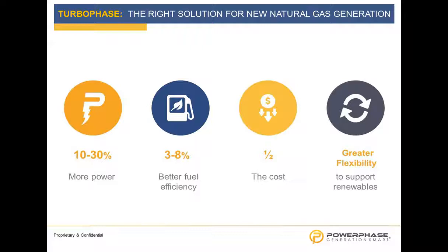Our desire here is to burn gas for more gas-fired generation, right? So we don't want to consume electricity or water. So we consume zero water and minimal electricity. And what results in this is a generic 10 to 30% more power, 3 to 8% fuel efficiency on the gas turbine. And as I just mentioned, we're about half the cost of a combined cycle per megawatt hour. And the biggest one is the most flexible solution.